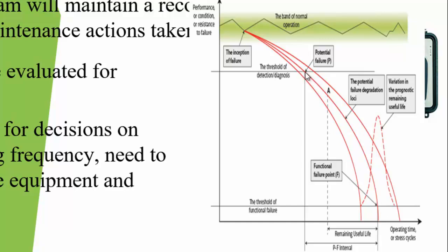Are we getting it? So when you come to this area, if you look at the trend, you can actually carry out what is called the fault prognosis. So you can carry out the fault prognosis. Assuming you give this time as the time that the equipment will fail, it can either fail before or after the time that you actually predicted.